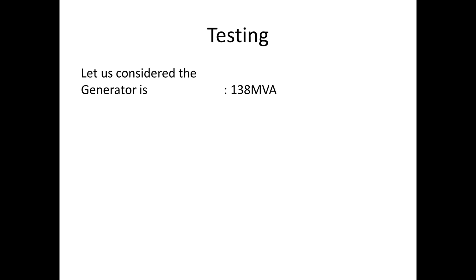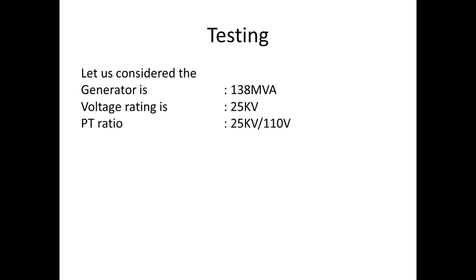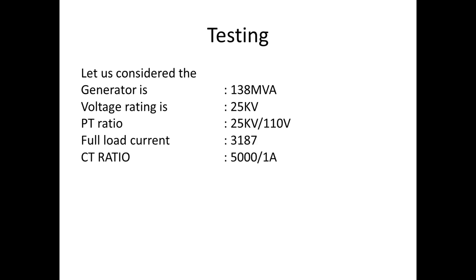Let us consider the generator is 138 MVA, voltage rating is 25 kV, and VT ratio is 25 kV / 110 volt. The full load current of the generator is 3187 amps, and the CT ratio is 5000 / 1 amps. Now we will see the relay settings.